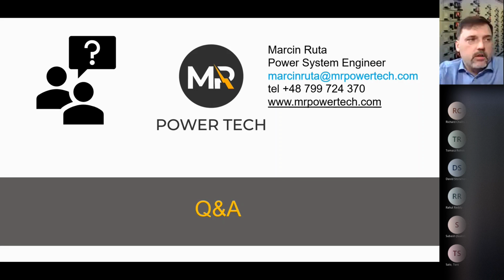But normally you treat all the calculation for arc flash the same, whether the doors are open or closed; generally we treat it as closed. So we don't differentiate, at least yet, between open and closed doors. I know there is a difference in pressure relief, but it's very complicated to calculate as well. And as a rule of thumb, if you operate the system, and I can show you the videos, sometimes it doesn't matter if the panel is closed, sometimes it doesn't matter if it is open. I think behind it is that when you operate it, you always do something with it. So probably it's half open, half closed. It's hard to predict this.